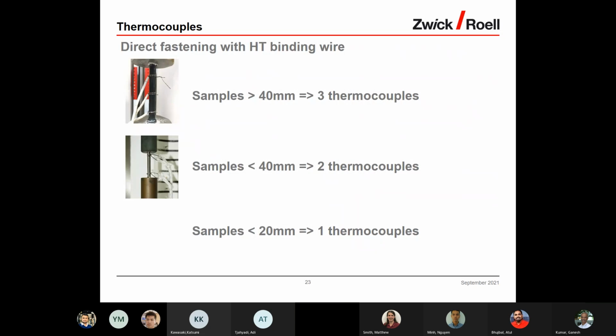Direct fastening with high temperature binding wire: for samples larger than 40 millimeters we take 3 thermocouples. For samples smaller than 40 millimeters, we use 2 thermocouples, and for samples smaller than 20 millimeters, we use 1 thermocouple.